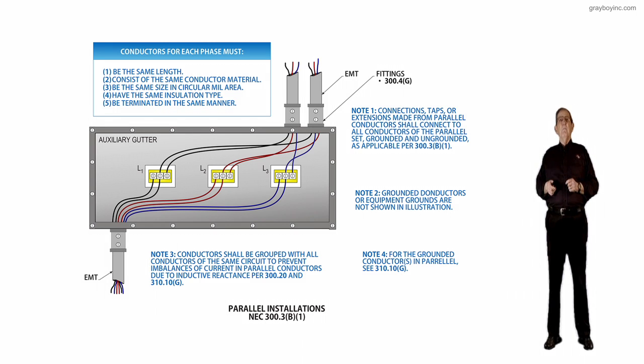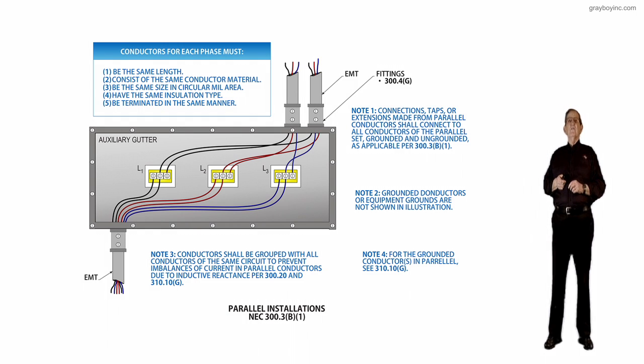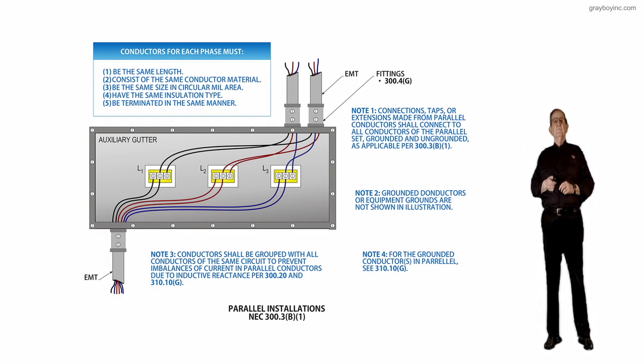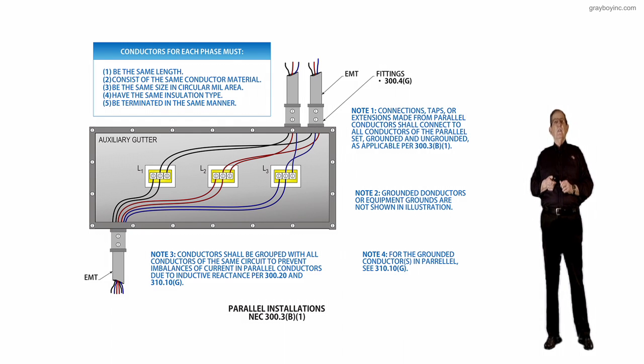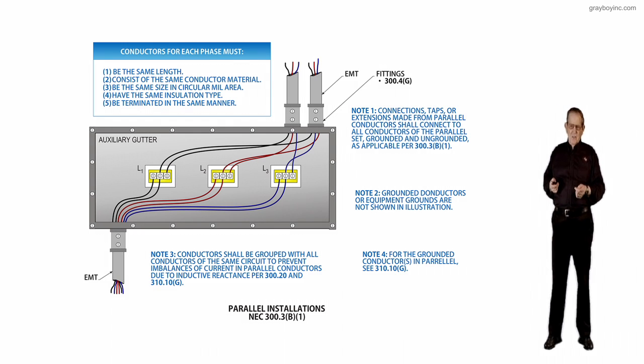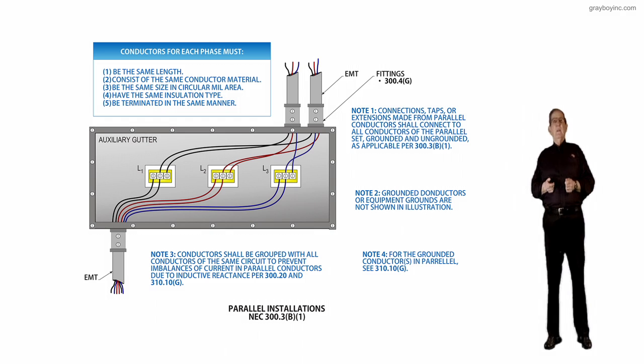In the boxed-in information, you have one through five listed items that must be complied with: be the same conductor length, consist of the same conductor material, be the same size and circular mill area, have the same insulation type, and be terminated in the same manner.